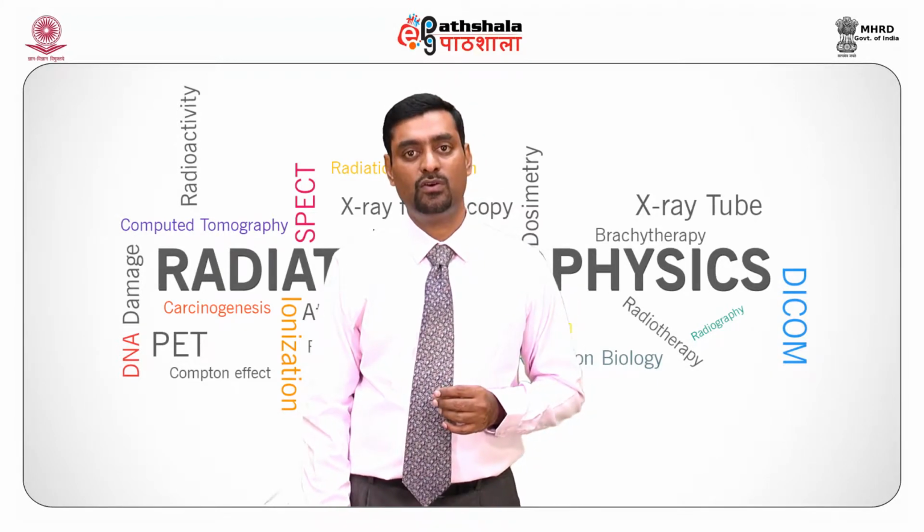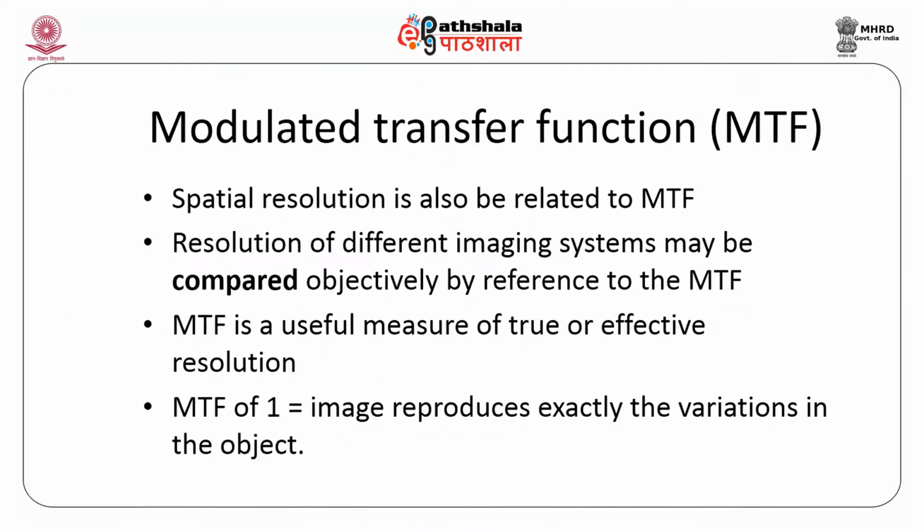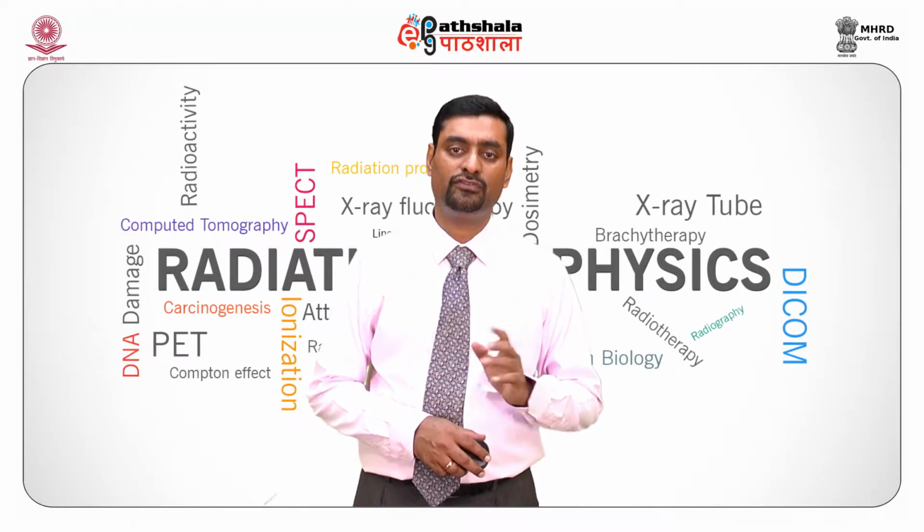The best method would be the modulation transfer function, which is called the MTF. So spatial resolution is also related to the modulation transfer function, MTF. The resolution of different systems may be compared objectively by reference to the modulation transfer function. The MTF is a useful measure of true or effective resolution. If MTF is 1, the reproduction of the image is exactly as that of the object.